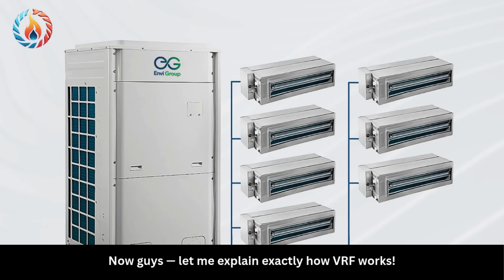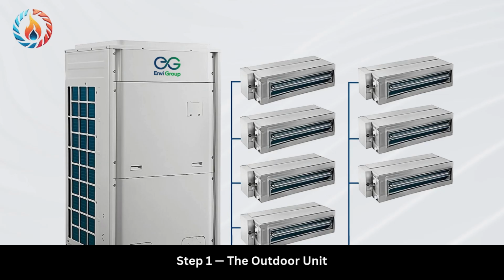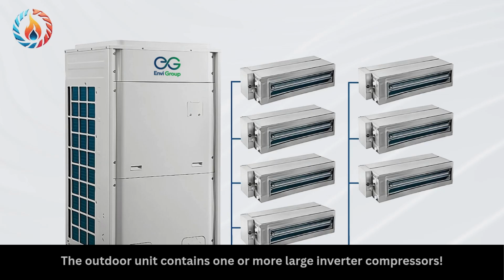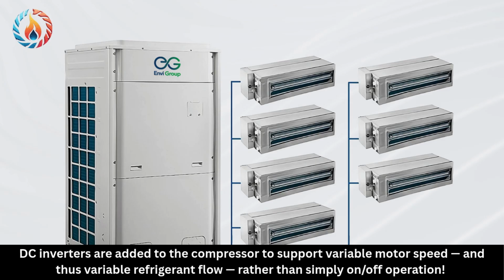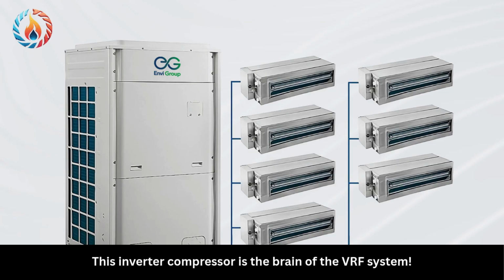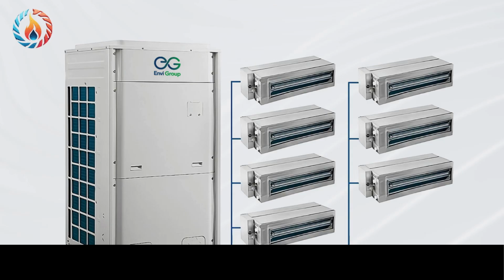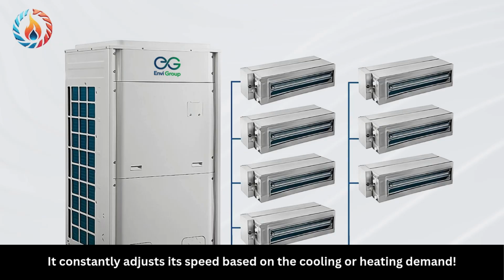How does a VRF system work? Now guys, let me explain exactly how VRF works. Step 1. The outdoor unit. The outdoor unit contains one or more large inverter compressors. DC inverters are added to the compressor to support variable motor speed and thus variable refrigerant flow, rather than simply on/off operation. This inverter compressor is the brain of the VRF system. It constantly adjusts its speed based on the cooling or heating demand.